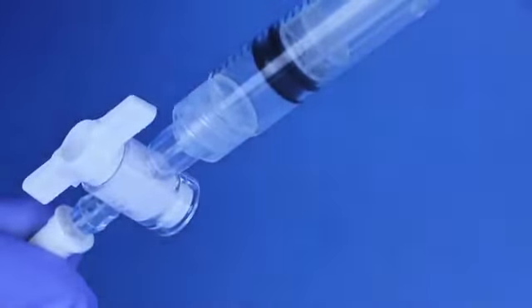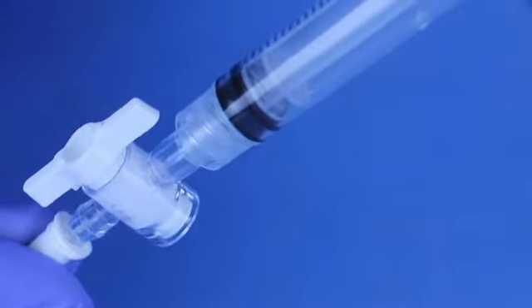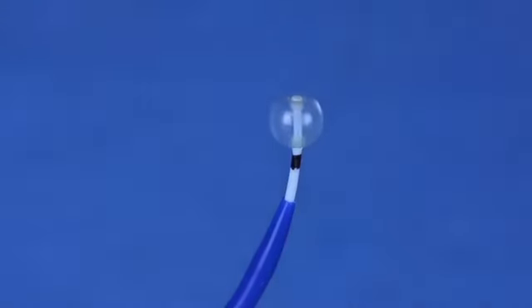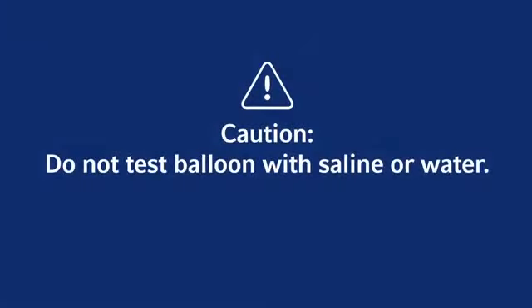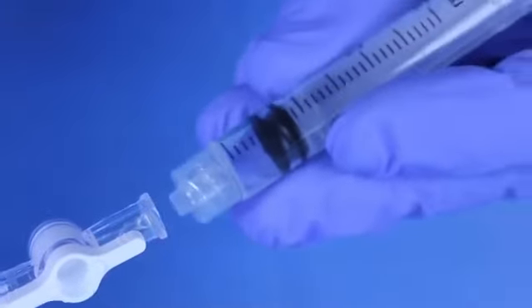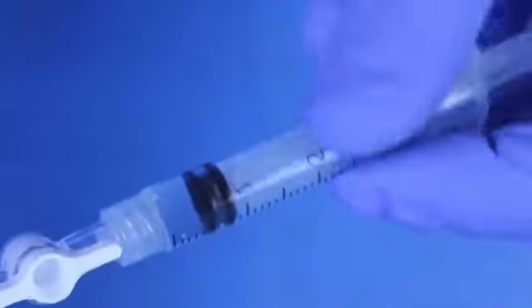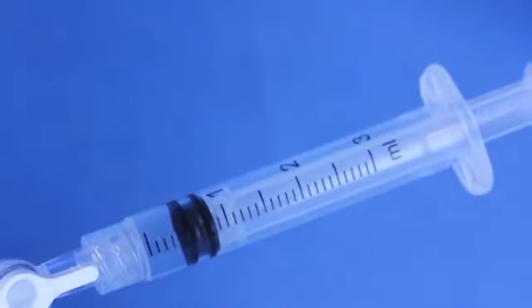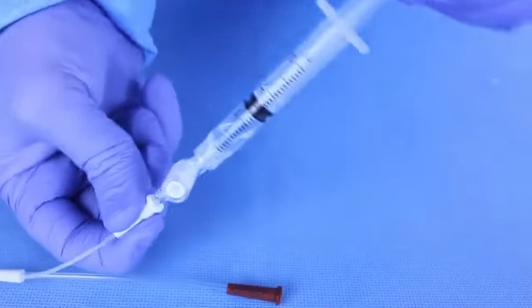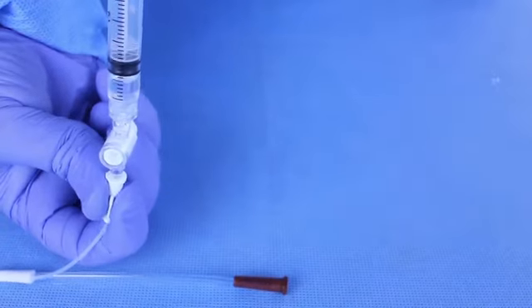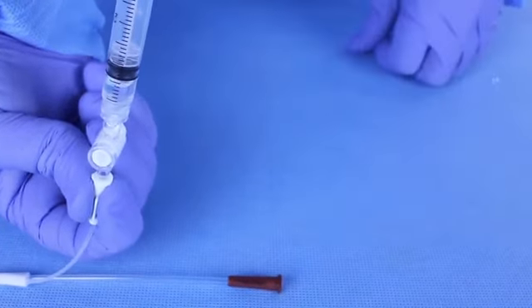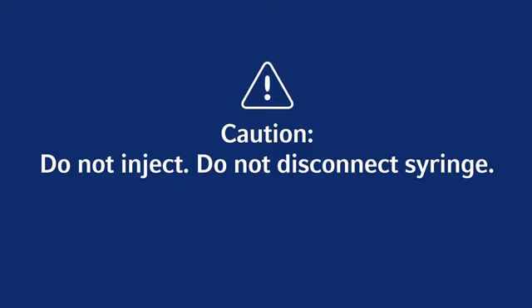To inflate balloon, open balloon stopcock by turning lever parallel to catheter. Inject 0.6 cc of air. Observe balloon for leakage. Deflate balloon and disconnect syringe. Caution: do not test balloon with saline or water. Fill syringe with 1/2 cc of sterile saline or water. Evacuate air from syringe and attach syringe to balloon lumen. Aspirate to evacuate air from extension line and stopcock. Position air pocket behind fluid in syringe. Caution: do not inject, do not disconnect syringe.